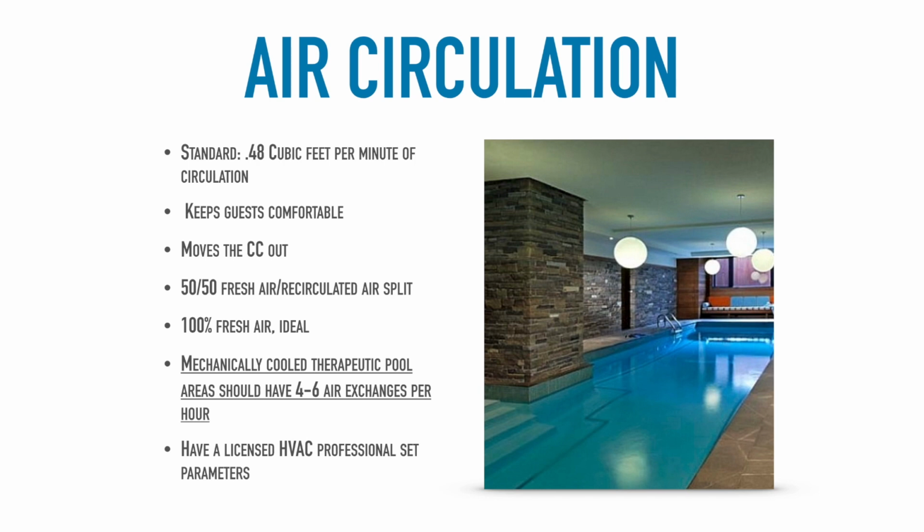Now, everybody, even if you're not setting your HVAC parameters, make sure you write this one down. Mechanically cooled therapeutic pool areas should have 4 to 6 air exchanges per hour. If you need to pause the video and write that down, feel free to do so. Mechanically cooled therapeutic pool areas should have 4 to 6 air exchanges per hour.